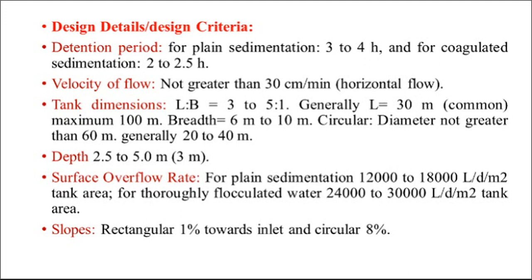Then surface loading rate for plain sedimentation tank, the surface loading rate should be 12,000 to 18,000 liter per day per meter square surface area of the tank.